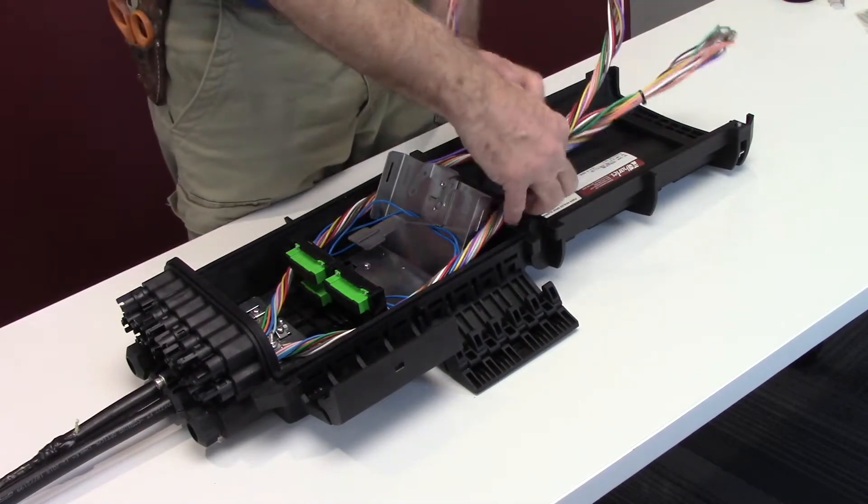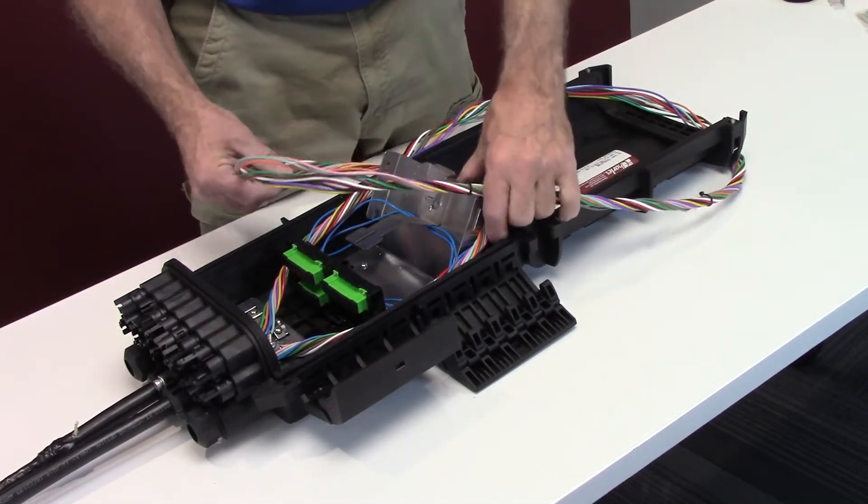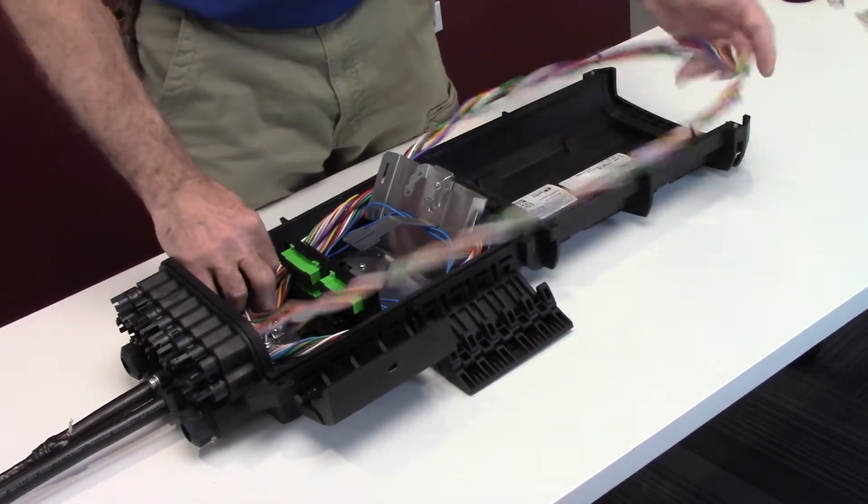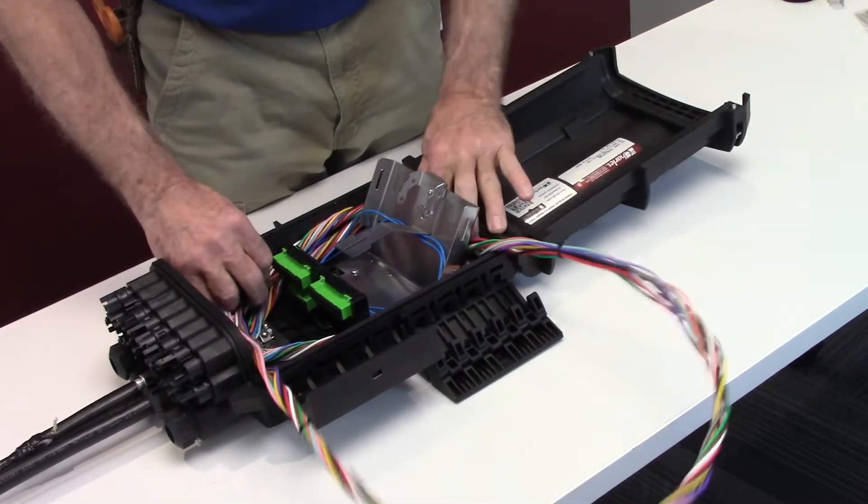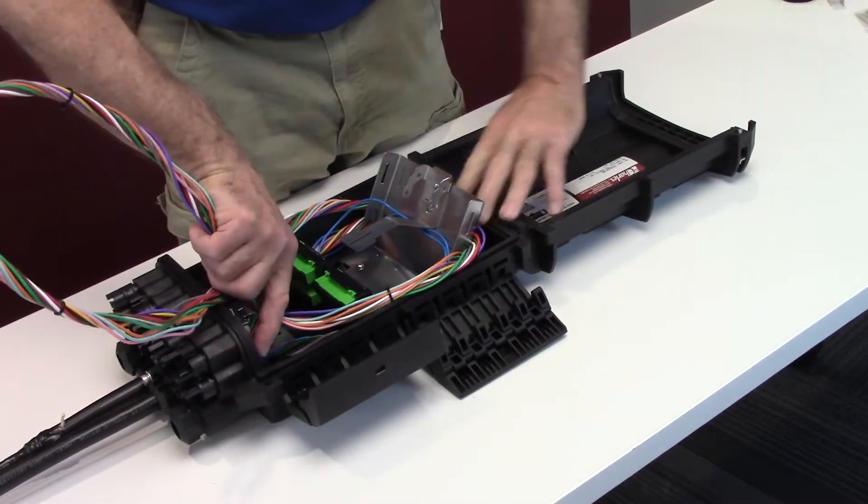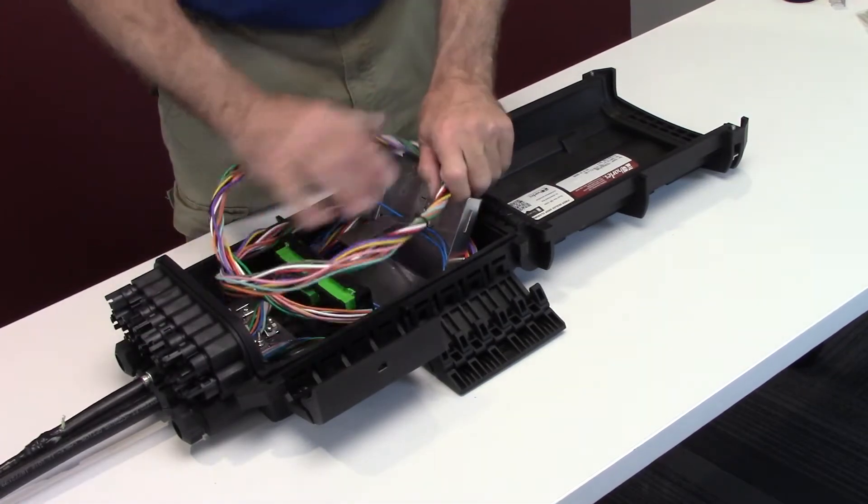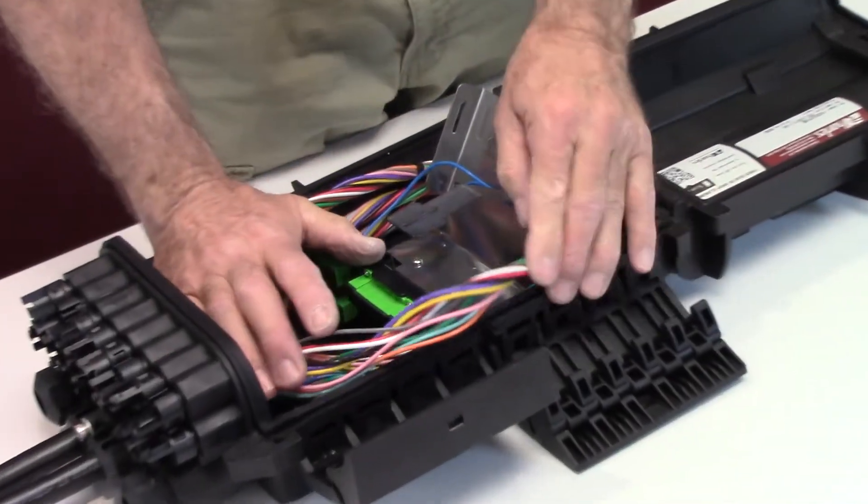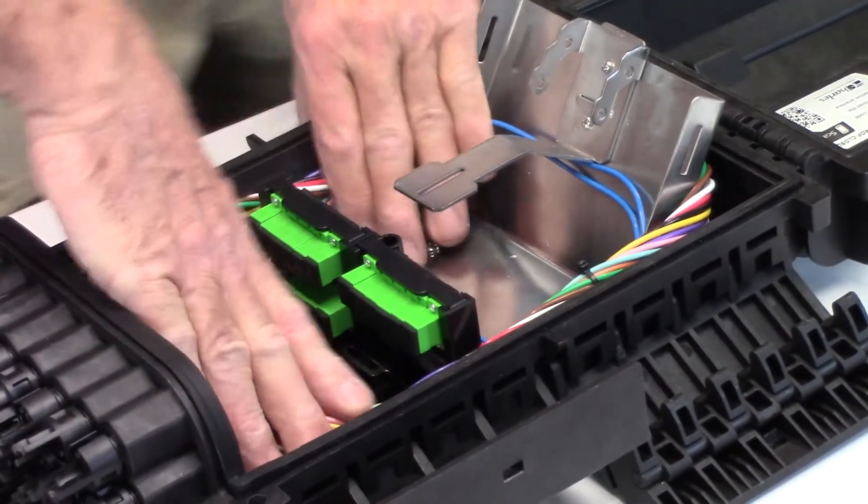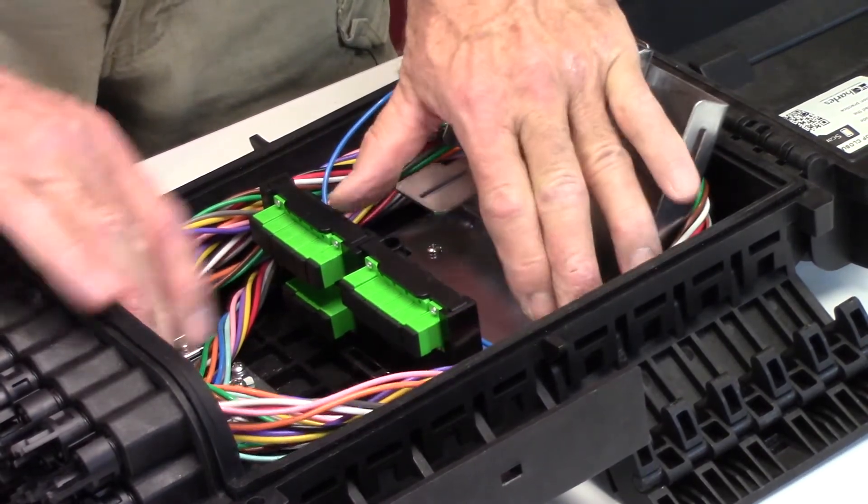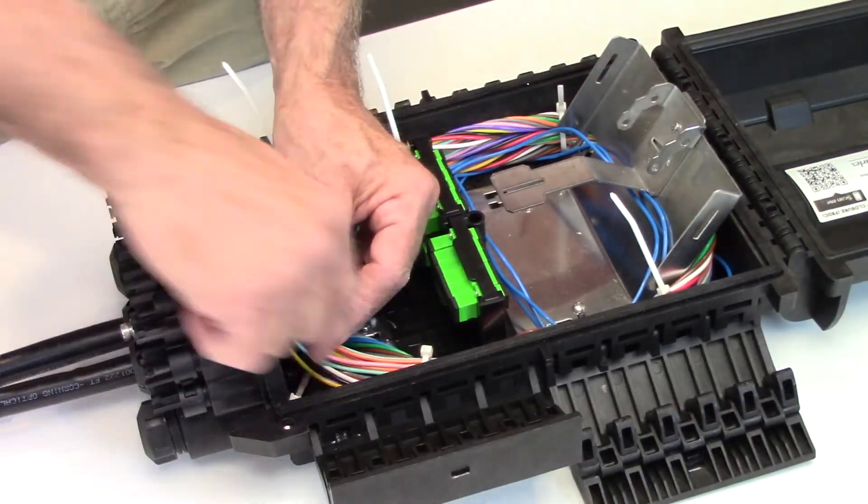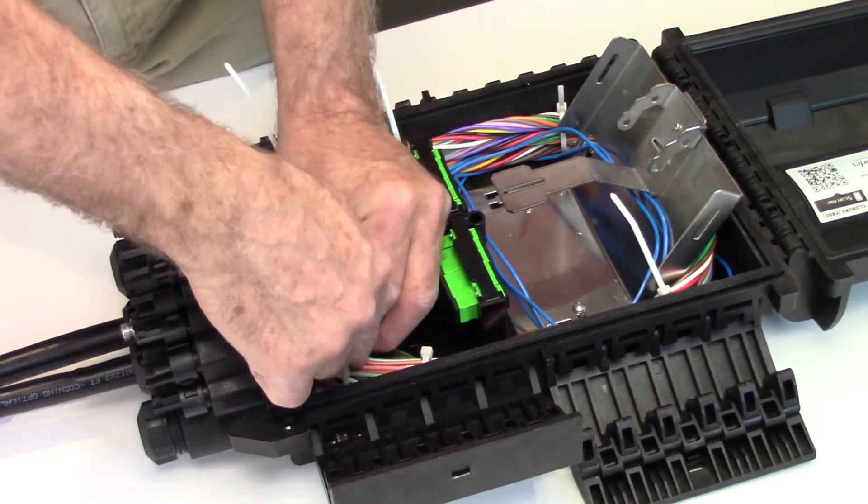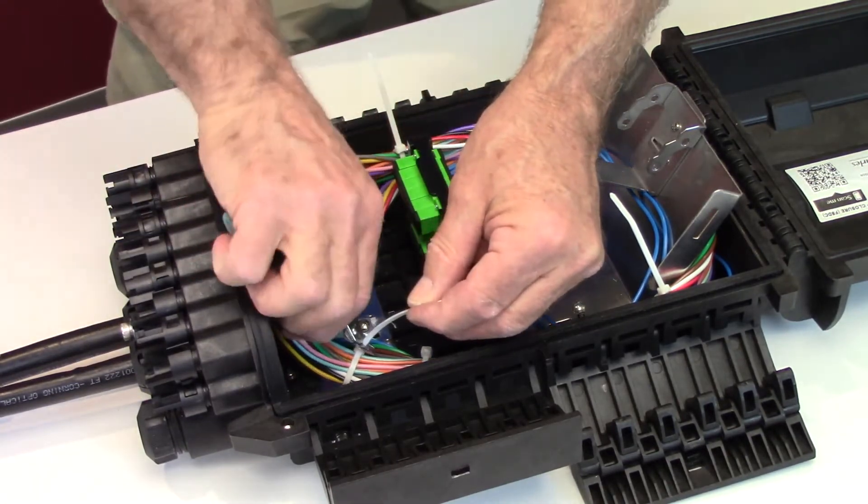Coil the express buffer tubes around the fiber storage basket, being careful that the tubes are not kinked. The 6 1⁄2 to 7 foot express length of the tubes will fit around the basket. Use cable ties to secure the expressed buffer tube coil around the fiber basket. The fiber coil should be stored below the edges of the FSDC.